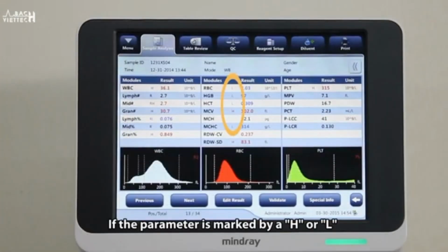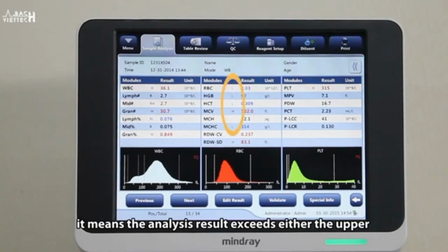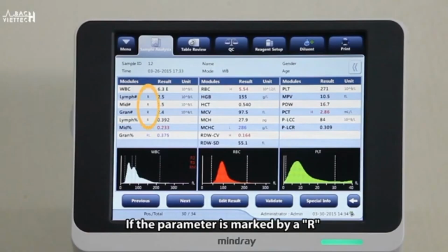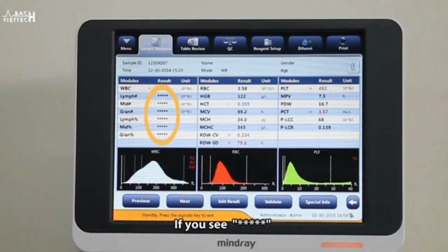If the parameter is marked by an H or L, it means the analysis result exceeds either the upper or lower limit of the reference range. If the parameter is marked by an R, it means the analysis result is questionable. If you see 5 asterisks as opposed to the result, it means the result is invalid.